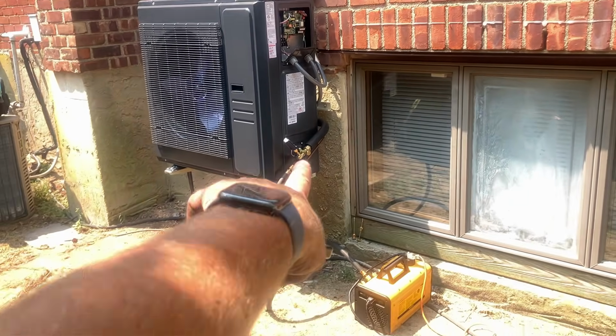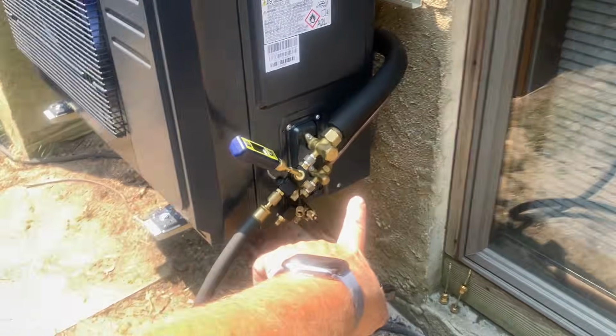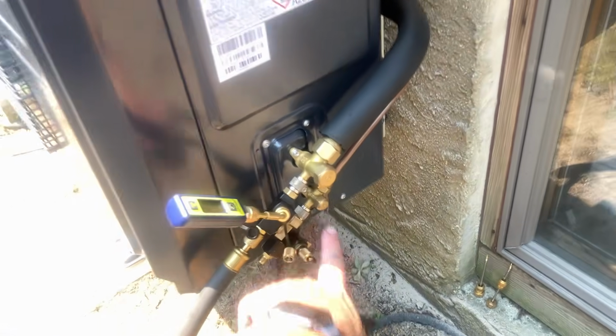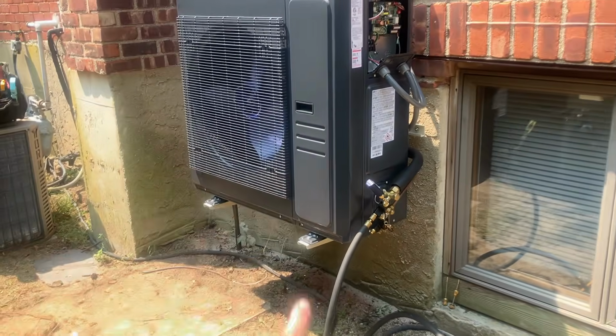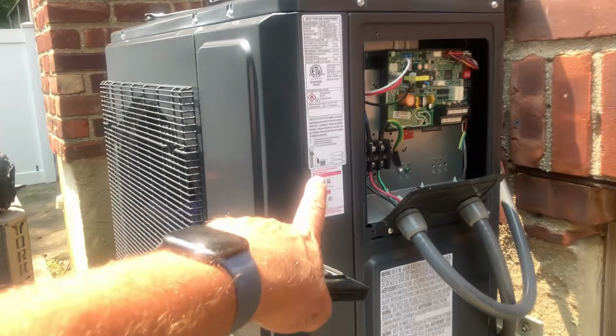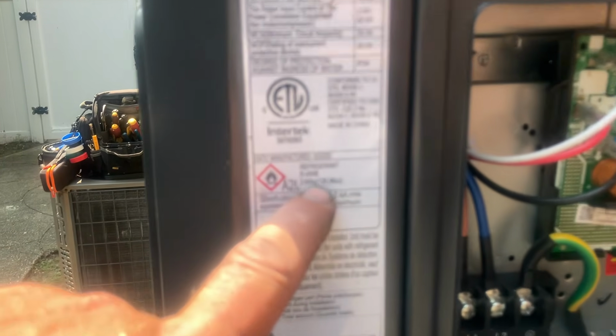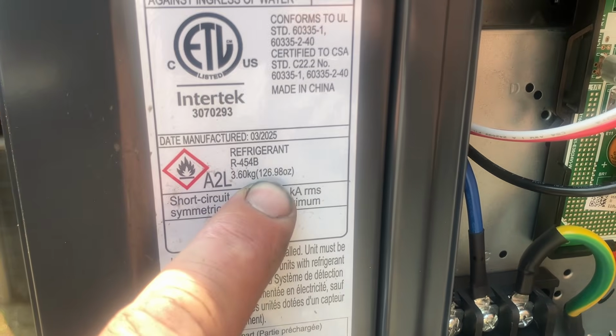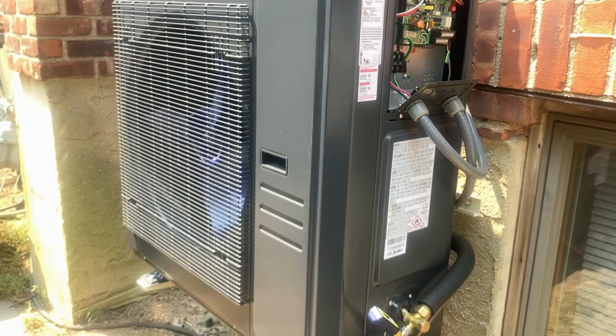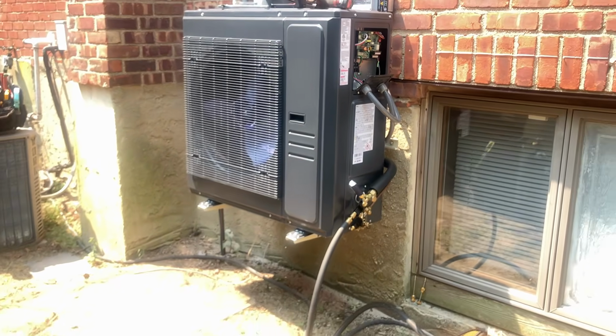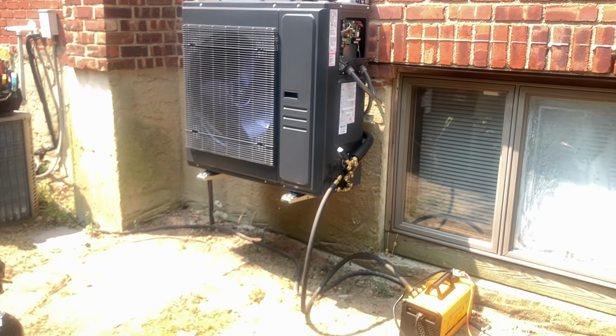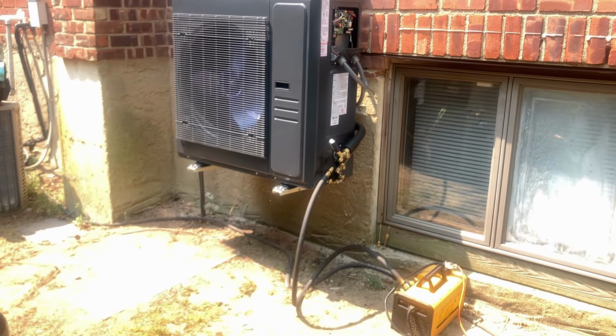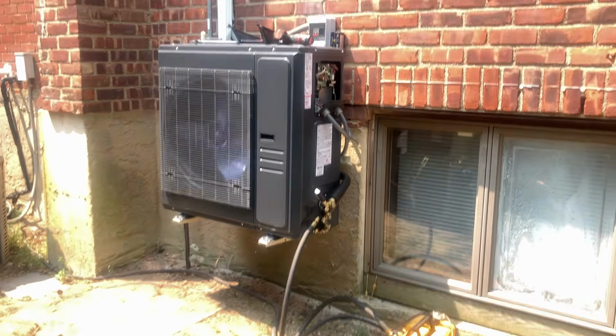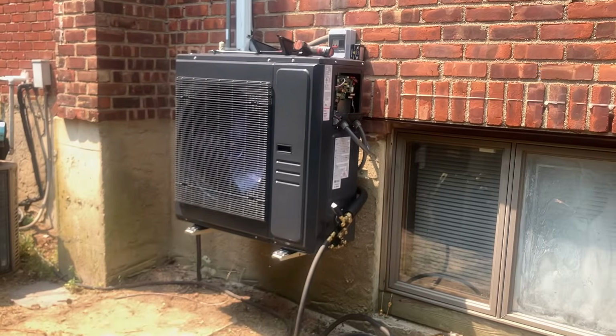The valves are closed. These service valves are closed, right? The system came pre-charged with refrigerant. In this case, it's R454B. And how much do we have here? We have 126.98 ounces. Look at that. So we're measuring the amount of moisture, air, and non-condensable gases that are left inside the refrigeration circuit, which consists of the line set and that evaporator coil.